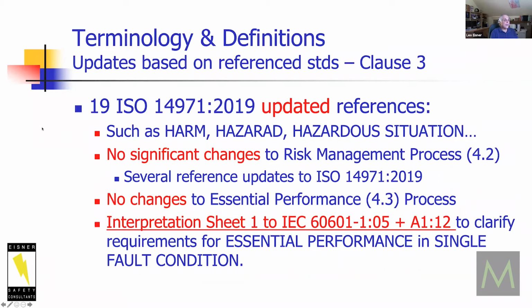So, quick note about terms and definitions. Risk management: because we went from the 2007 version of the standard to the 2019 version of 14971, some people are going, oh no, we have lots of changes, right? Well, the changes weren't really that bad. Yeah, some of the words, harm, hazard, and hazardous situation in 14971 changed. So all those references point back to 2019, and some of the definitions are a little different. But the base of the 601 standard really didn't change. So the risk management process itself, there was no significant change.